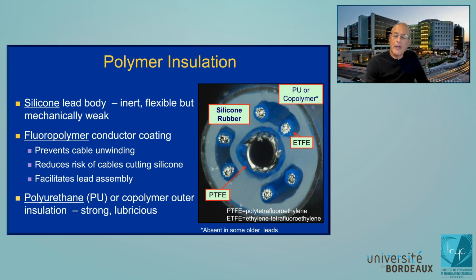I want to spend a minute on the insulation because you hear about different types of insulation. But broadly speaking, most of the insulation in the body of leads is always silicone. The great thing about silicone is it's very flexible, biostable and biocompatible. The downside, we'll get to this, is that it's mechanically weak. The silicone in the heels of your shoes wears out over time. I'm getting ahead of myself here, but we call that abrasion. And it's subject to various types of mechanical deficiencies.